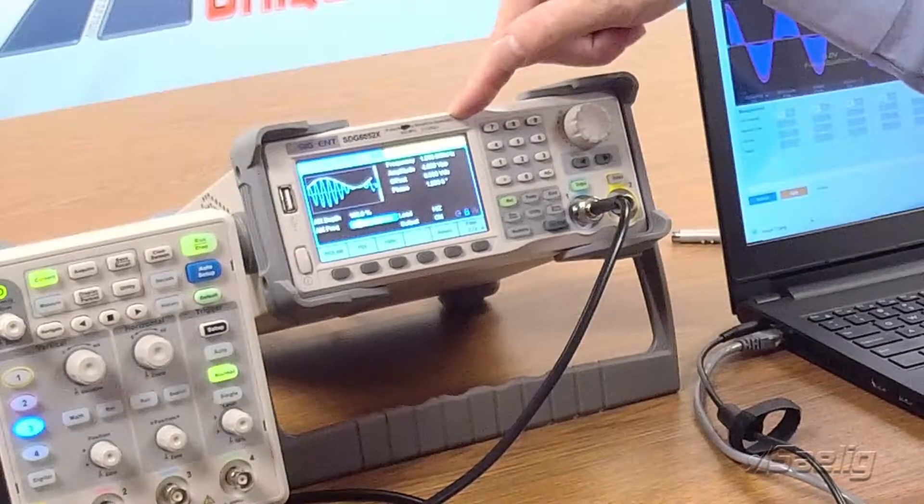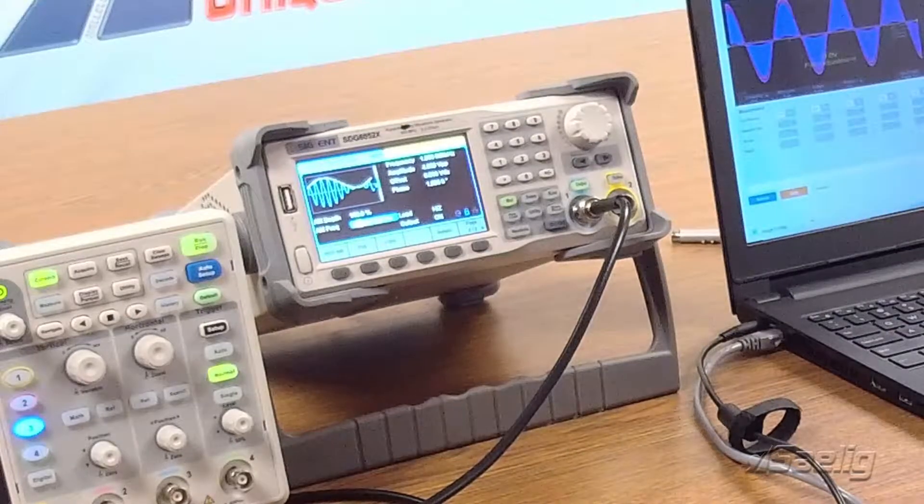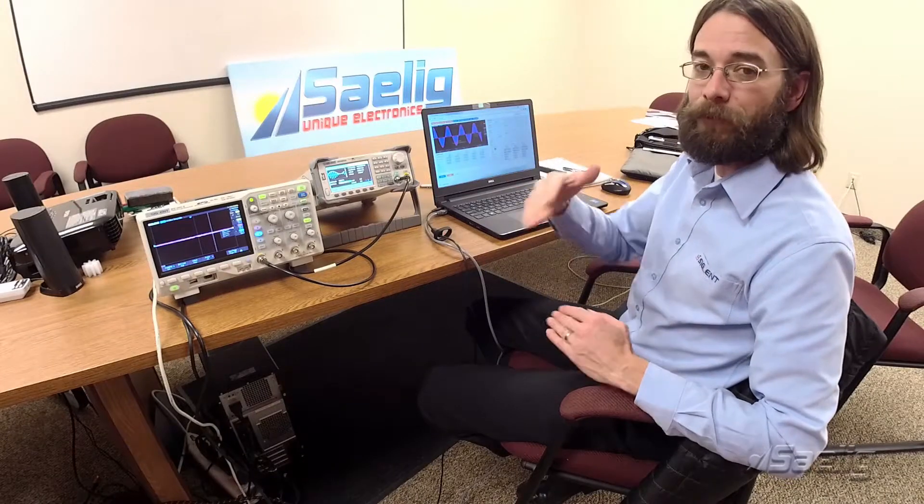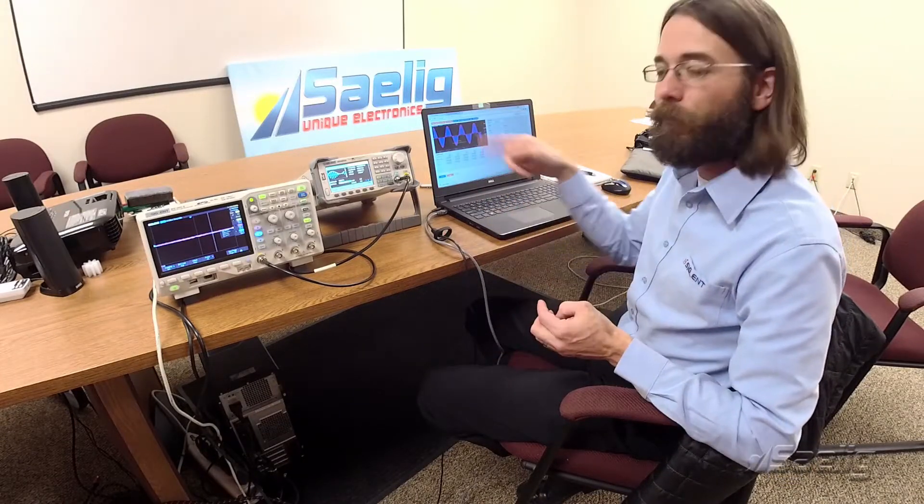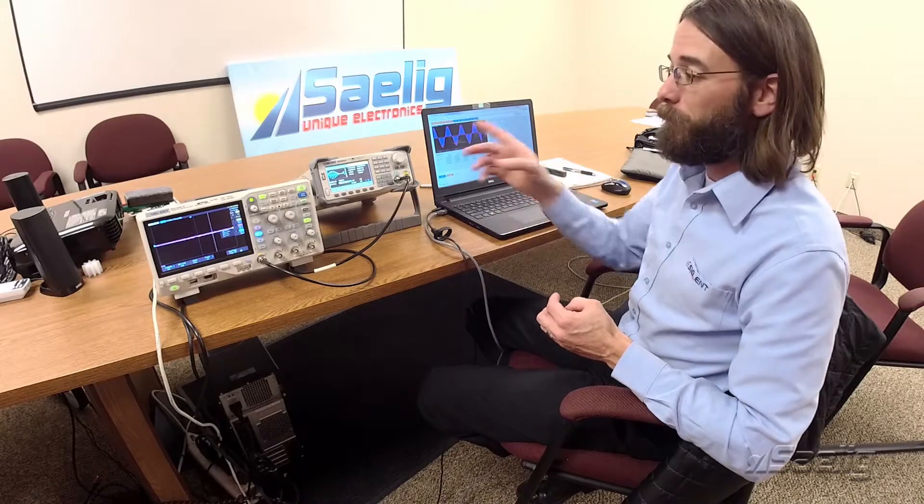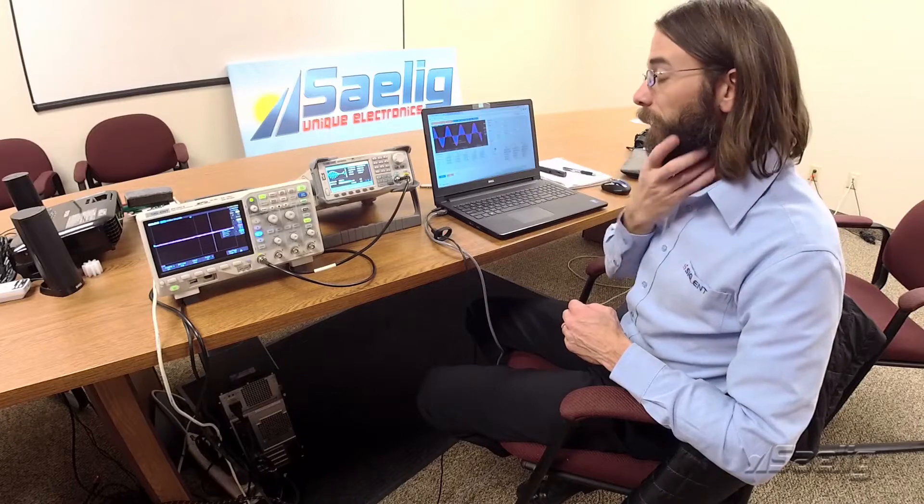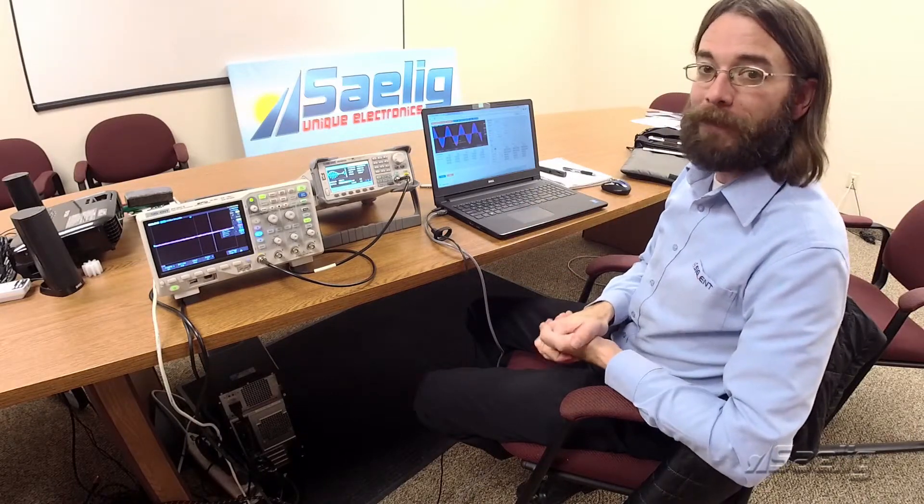This is also capable of doing very high frequency. So up to 500 megahertz, we're still capable of a very high amplitude. So typically as you get higher and higher in frequency, it's more difficult to support that particular output waveform at higher amplitudes. I believe we're up to 5 volts peak to peak at 500 megahertz on this particular instrument. So quite a lot of capability packed into this new box.